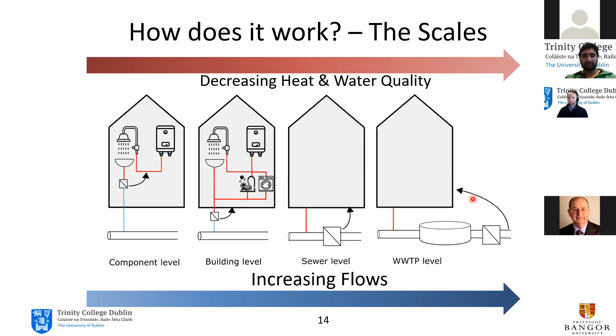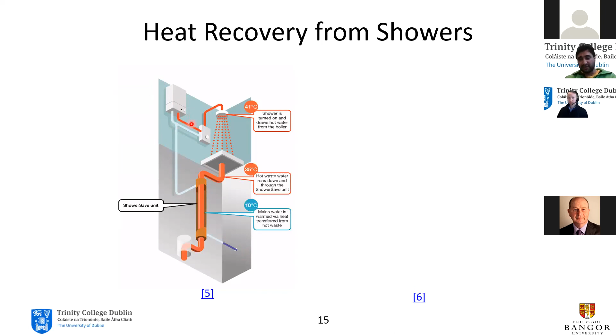This is an example of a shower system, in our domestic purposes as well as in the hospitality sector, where a vertical type of heat exchanger is placed in the drainage system. The cold water supply, the clean water coming from the bottom, is at almost 10 degrees Celsius, and the hot wastewater coming from the bathing tub is at a higher temperature. So it will recapture the heat from the hot wastewater and go directly to the auxiliary heating unit to reduce its heating load requirements. So via a mixing valve, we can save our monthly electricity bills.